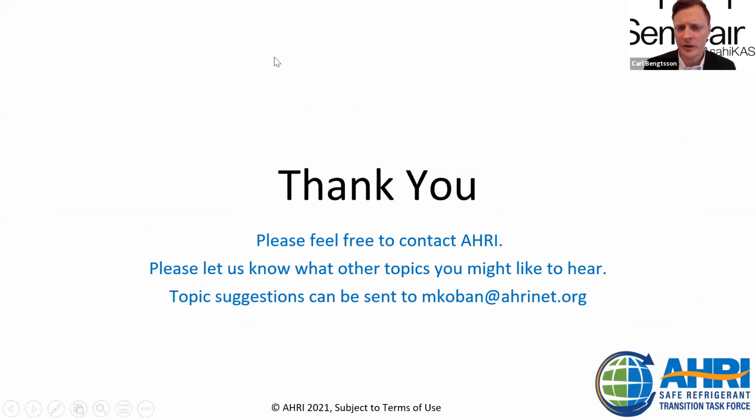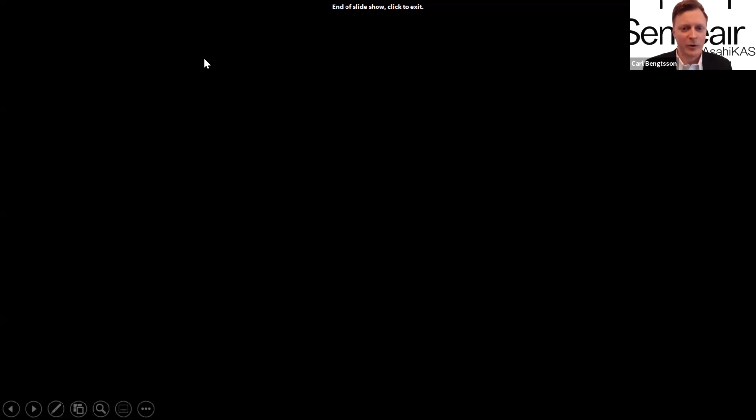So I think it was Edwin who asked about the lubricants that are also pumped around in the coils, and yes, within the Annex LL, you have both the test table of disturbance gases to ensure that your RDS system or your sensing system is not implicated by those disturbance gases or by poisoning. But of course, you also have the actual testing requirement for the sprays, which is going to be part of this nationally recognized testing laboratory methodology. So we're already building the RDSs to be immune to this. So I hope that answered the question. Edwin, you can't reply, but I hope that answered the question.